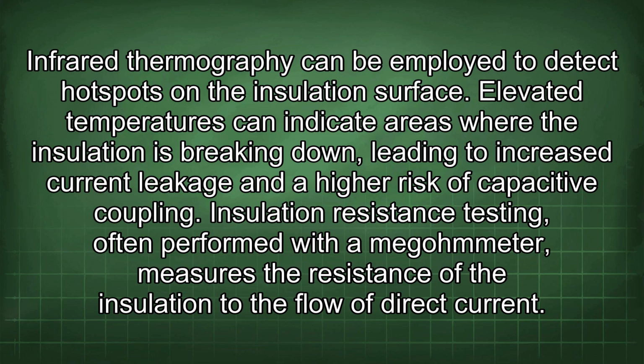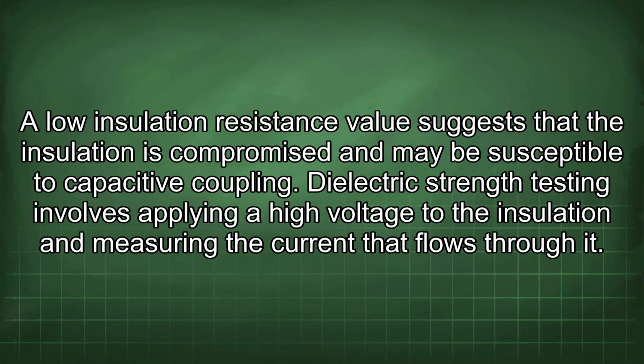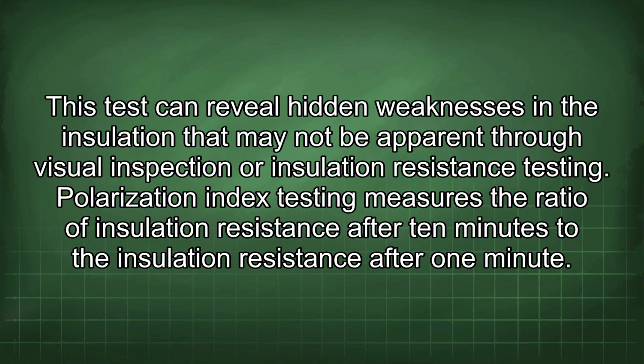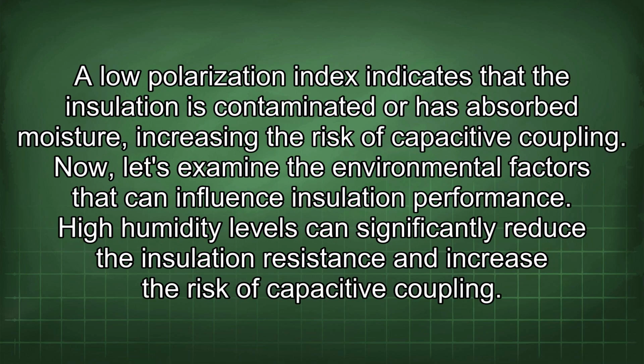of capacitive coupling. Insulation resistance testing, often performed with a megohmmeter, measures the resistance of the insulation to the flow of direct current. A low insulation resistance value suggests that the insulation is compromised and may be susceptible to capacitive coupling. Dielectric strength testing involves applying a high voltage to the insulation and measuring the current that flows through it. This test can reveal hidden weaknesses in the insulation that may not be apparent through visual inspection or insulation resistance testing. Polarization index testing measures the ratio of insulation resistance after 10 minutes to the insulation resistance after 1 minute. A low polarization index indicates that the insulation is contaminated or has absorbed moisture, increasing the risk of capacitive coupling.